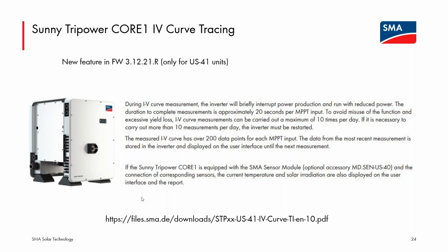Great. Does the CORE1 require a neutral? It does not. So I don't have any wiring diagrams in here, but on the AC side, you have the 2-inch knockout, and you have conductor terminals for line 1, line 2, line 3, and neutral. There is, in fact, a jumper that bonds the neutral terminal to the body of the inverter installed at the factory. The inverters, and this is the important statement, each and every CORE1 US must connect to a 277/480 grounded Y service. In operation, it does not burden the neutral with any current. It is using the measurement at that neutral terminal as a reference to ground. So while it must connect electrically to a 277/480 grounded Y service, it does not need the neutral to be brought to it to operate.